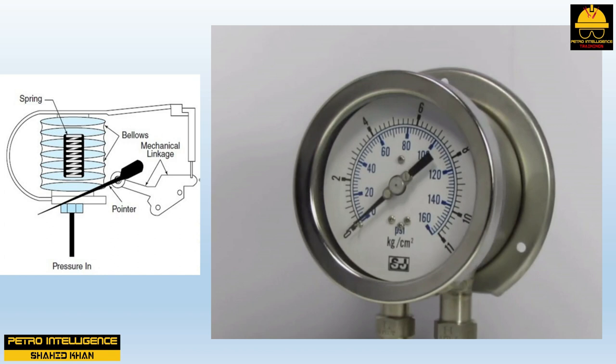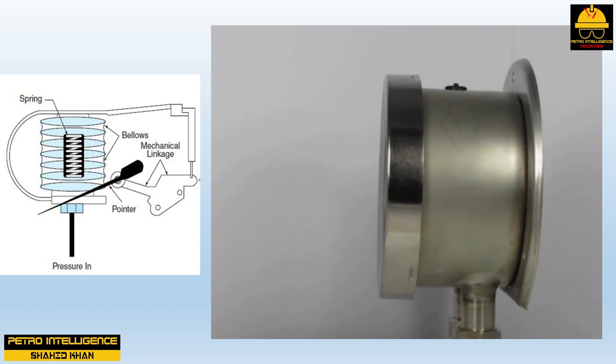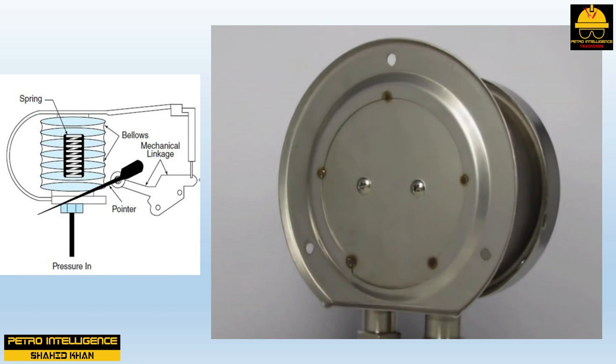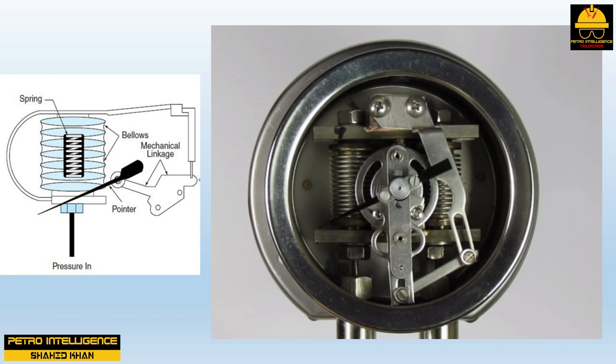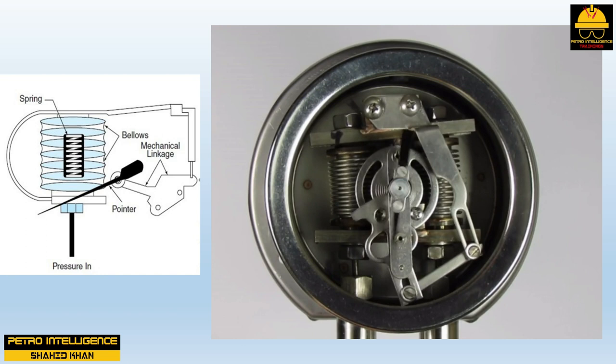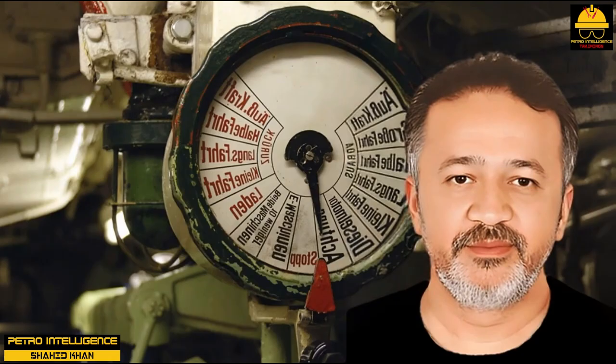A bellows pressure element consists of an accordion-type bellows, a spring that resists expansion, a pressure inlet, a mechanical linkage, and a pointer. During operation, pressure admits flow into the bellows; as the bellows expands, tension on the spring increases and the mechanical linkage moves the pointer. If pressure is reduced, the spring forces the bellows back to its original position.